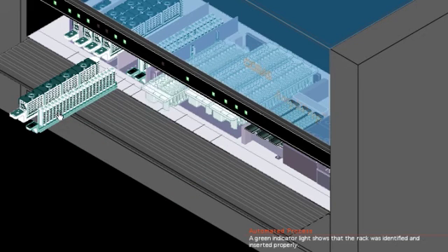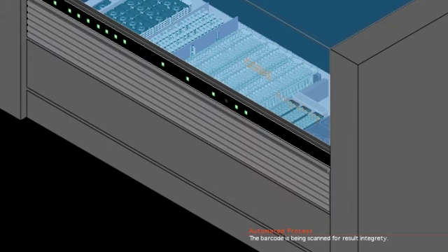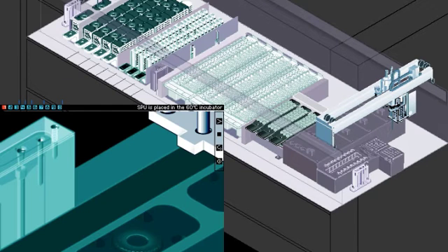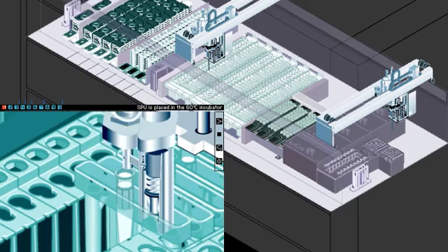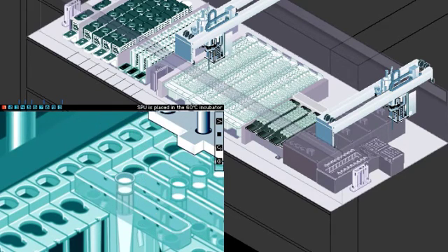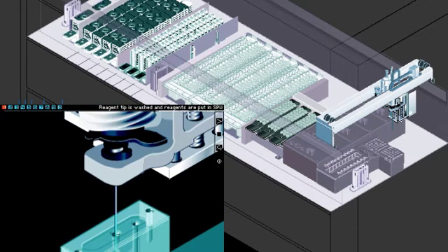place the reagent and patient sample racks into the Ampliprep system. Here's how it works. The left transfer arm moves the sample processing unit into a 60-degree incubator. The reagent tip is washed every time it pipettes a reagent.